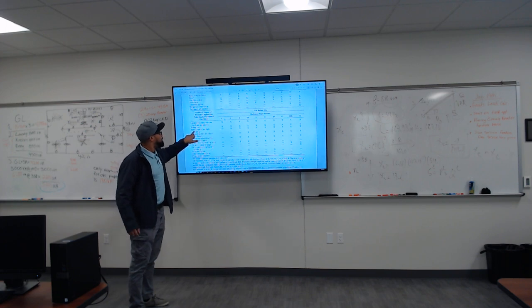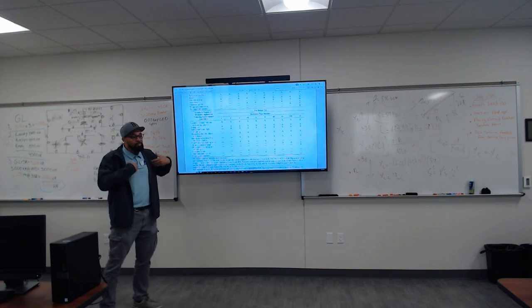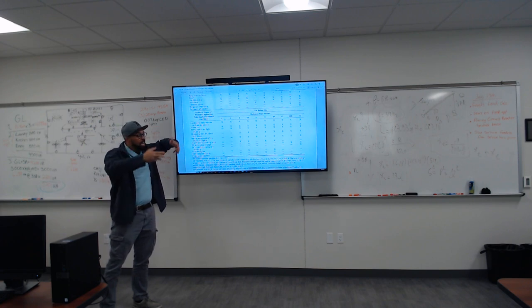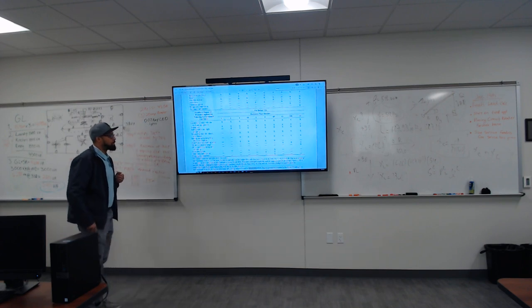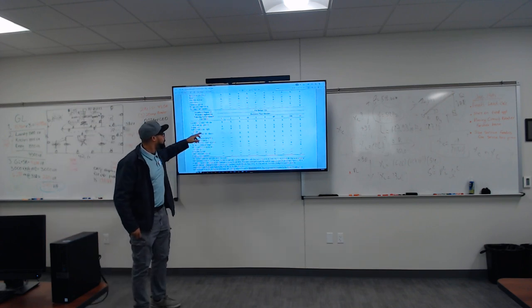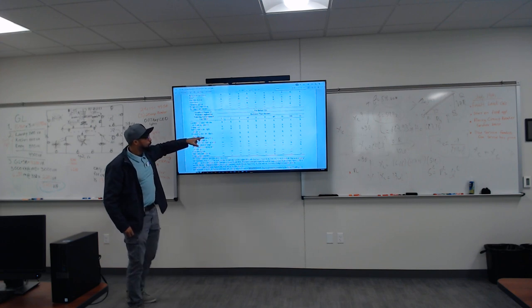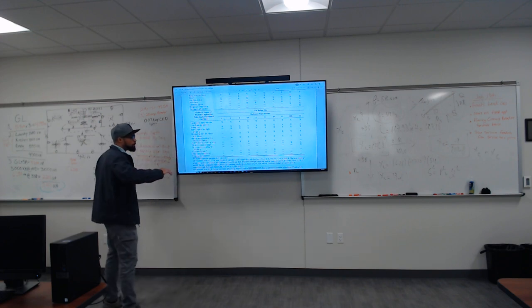So, number one, falling liquids and liquid splashing. If you have a counter, like I have in my garage, I have shelves and whatnot like that, but I don't have it above my service panel. But if I have some liquids above my service panel, and it was a number one style or type, this cannot withstand any falling liquids or light splashing. But the rest of them do. So as you progress, that's each type of condition heightened, fewer and fewer service panels can prevent from being harmed from them.